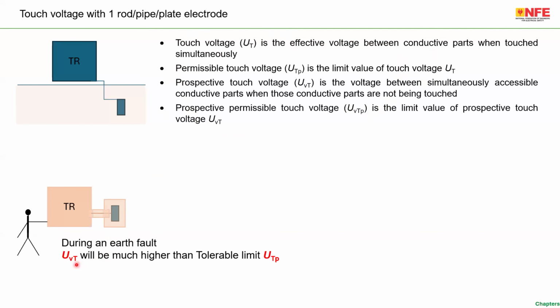So here you can see the definitions of these terms, UVT, UTP, and so on. UTP is the permissible touch voltage. It is the maximum limit of the touch voltage. UVT is the prospective touch voltage, which is the voltage between simultaneously accessible conductive parts when those conductive parts are not being touched. So basically, the prospective touch voltage is much higher than the tolerable limit. As a result, people get shocked.